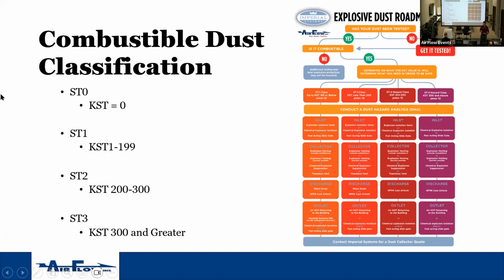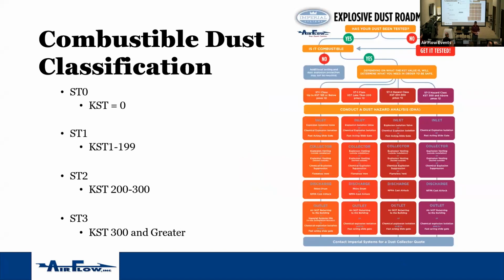There are different dust classes. There's ST0, which would be a KST of 0. There's ST1, which is your KST up to 199. And ST2, which is between 200 and 300, and ST3, a KST of 300 or above. A lot of this stuff, if you look at it, underneath on the dust hazard analysis, right underneath the orange bar that goes the full side back and forth, the KSTs are all listed in 4 columns underneath there. ST1, ST2, and ST3. It'll give you what you need to do on your inlet for protection.